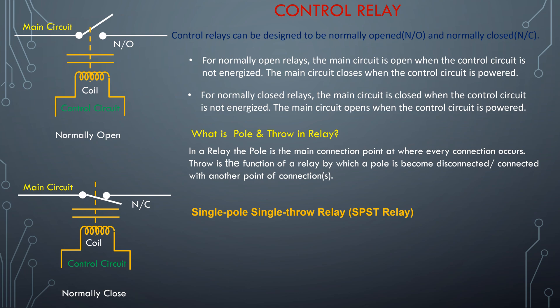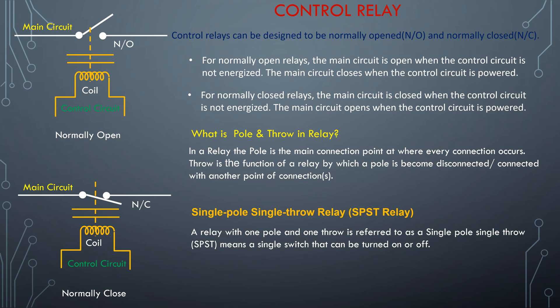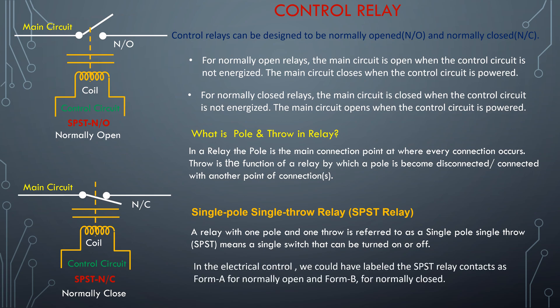Single pole, single throw relay — SPST relay. A relay with one pole and one throw is referred to as a single pole, single throw SPST. It means a single switch that can be turned on or off. In electrical control, we could label the SPST relay contacts as Form A for normally open and Form B for normally closed.